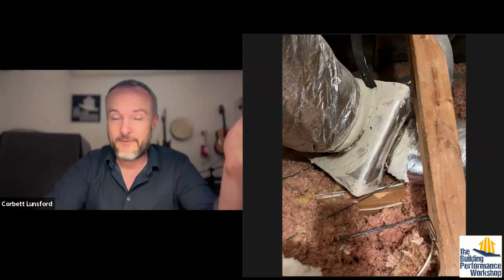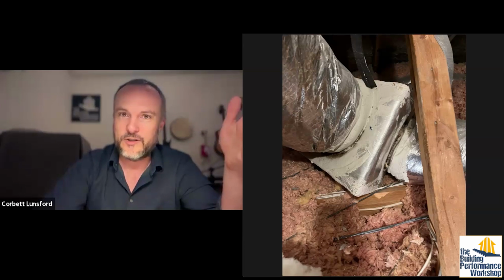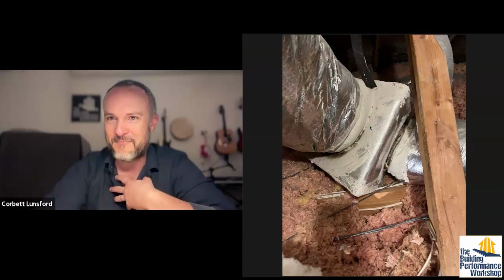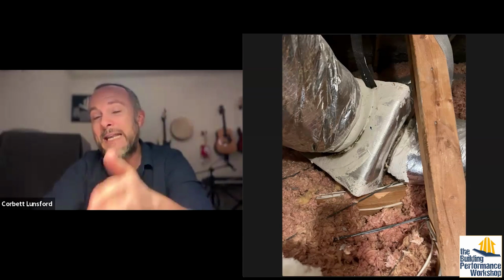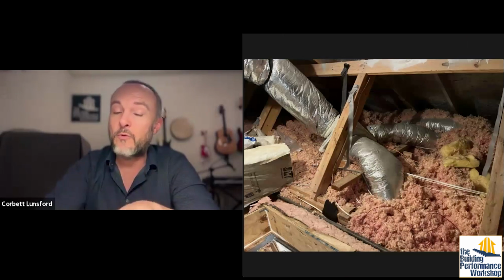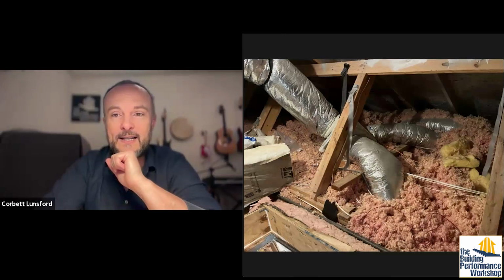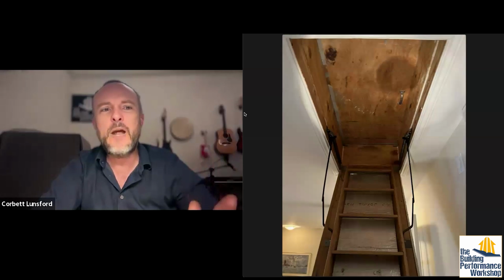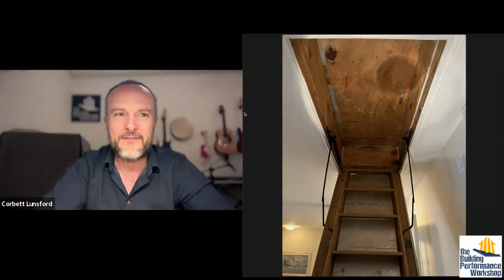And the good news for those of you who have ductwork that is in an attic, even though an attic is the worst place to put ductwork generally when you're talking to somebody like me or Zach, is that you can get at that and you can clean it. You can replace it. And that's one of the things that I'd like to ask you about in a few minutes here. You can rewrap this, we can rerun it, we can do anything that we want to. We can then affect things about the enclosure itself as well.